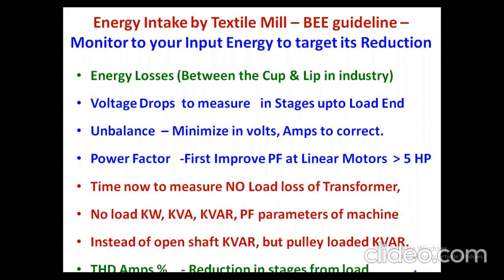If it is done for all the machines, motors above 5 HP, then automatically the voltage drop is definitely going to reduce, and it will be almost on par. End to end, the drops will be a maximum of 5 to 10 volts only. Then comes the unbalance in voltage.